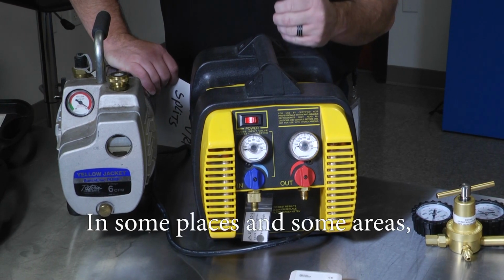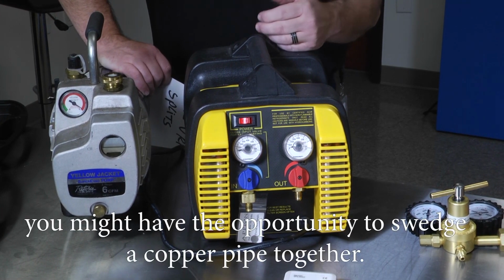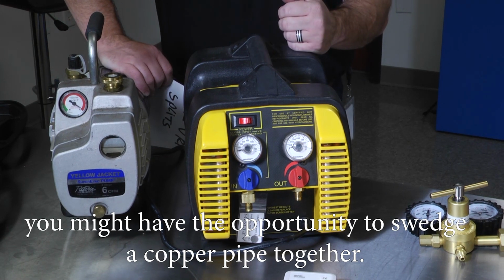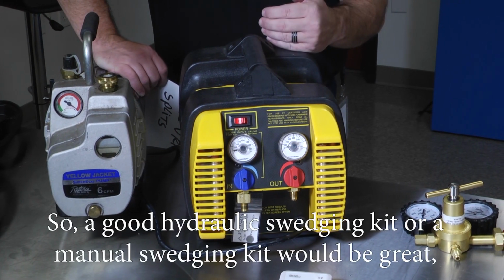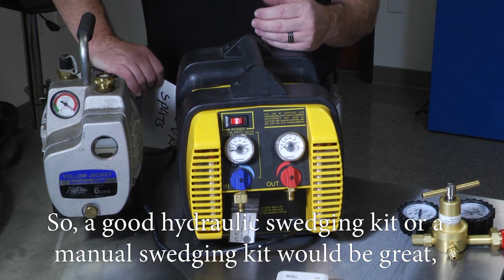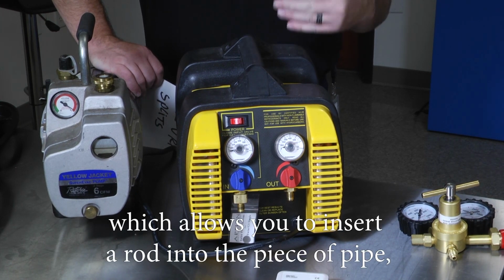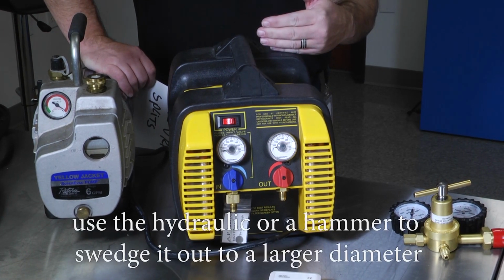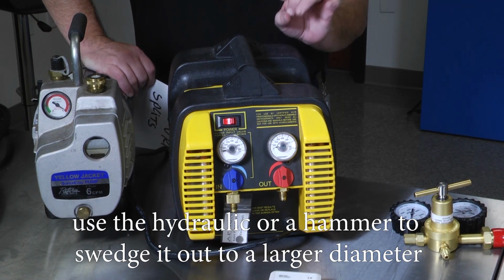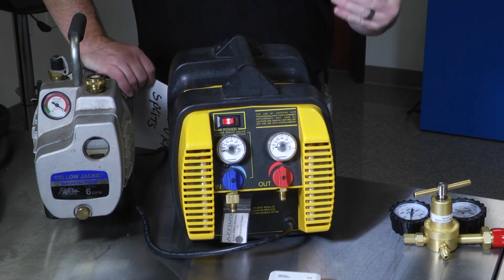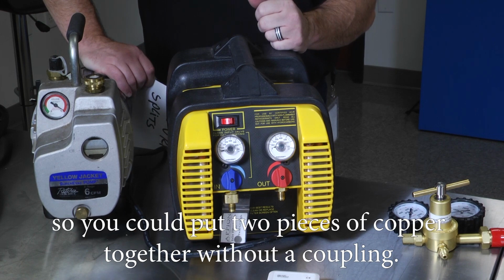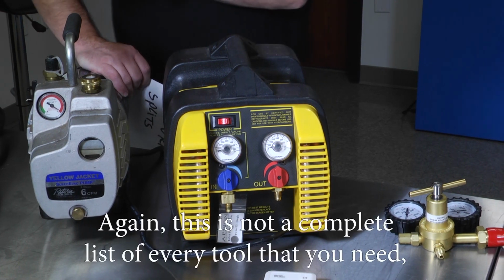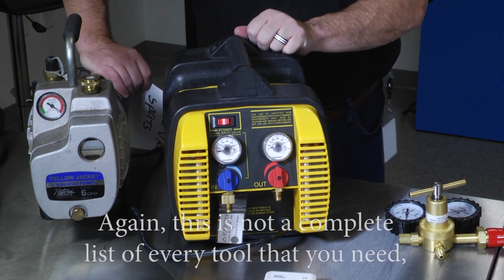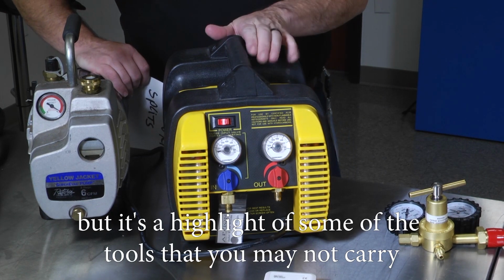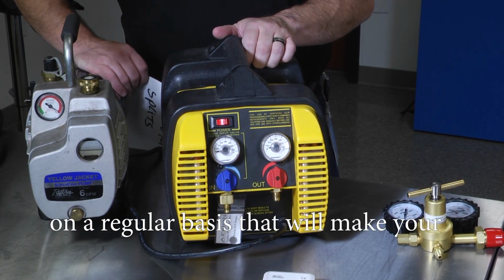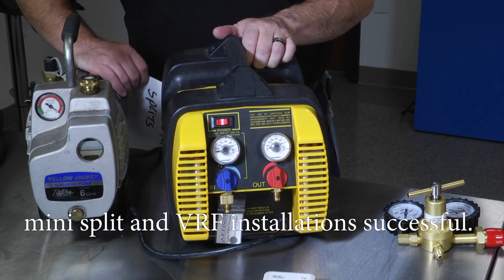In some places, in some areas, you might need to have the opportunity to swedge a copper pipe together. So a good hydraulic swedging kit or a manual swedging kit would be great, which allows you to insert a rod into the piece of pipe, use the hydraulic force or a hammer to bend it, to swedge it out to a larger diameter so that you can put two pieces of copper together without a coupling. Again, this is not a complete list of every tool that you need, but it's a highlight of some of the tools that you may not carry on a regular basis that will make your mini split and VRF installations successful.